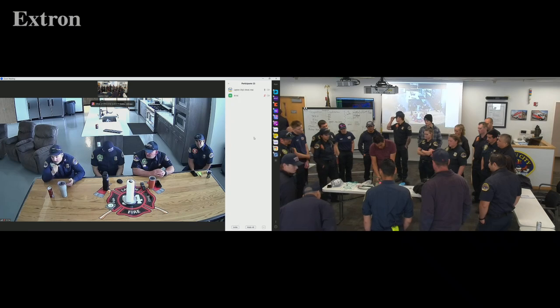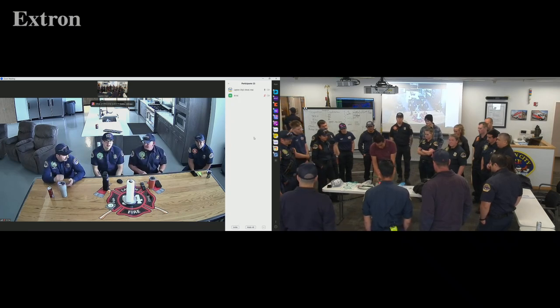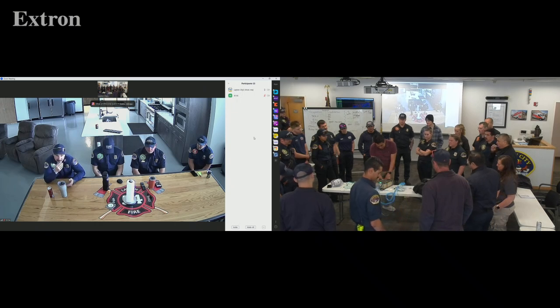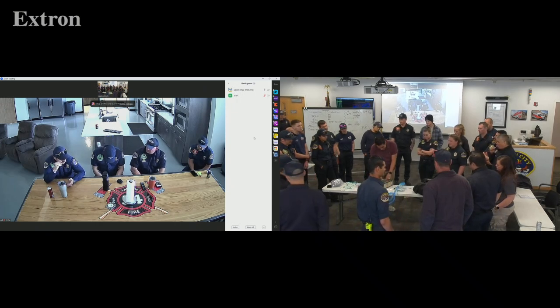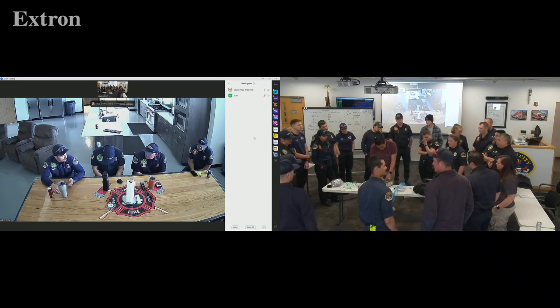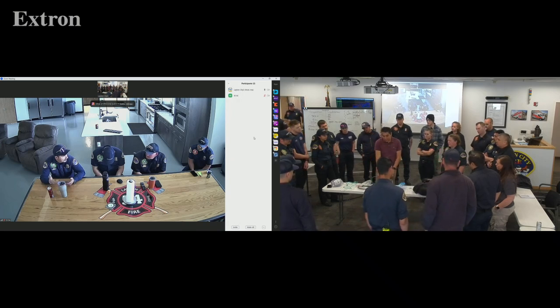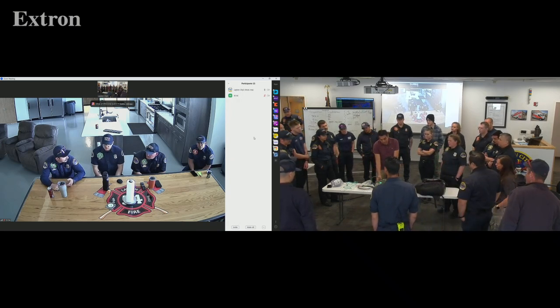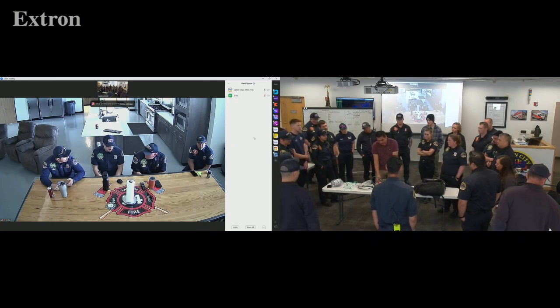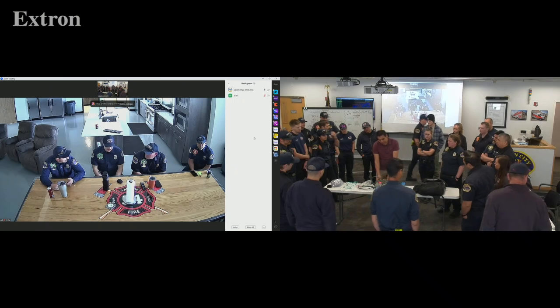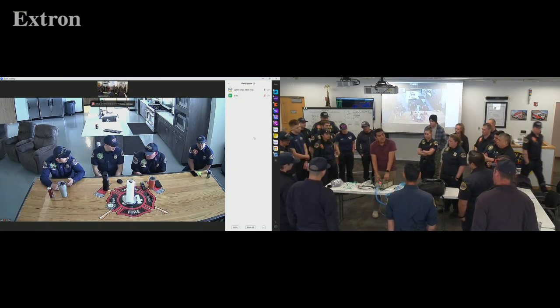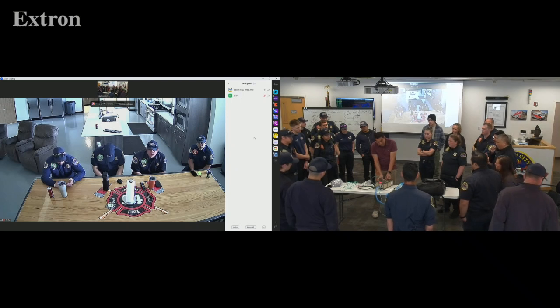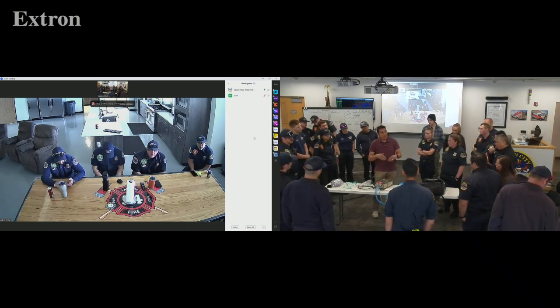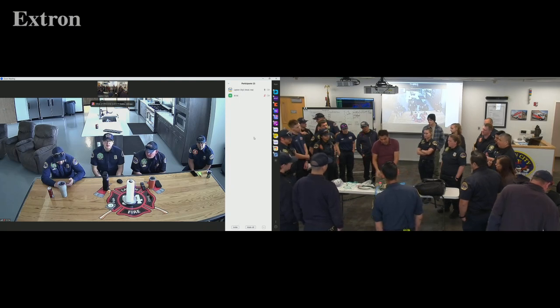Come on, change the mode. I keep forgetting that you have to push forward. So once you choose bi-level, in the bottom right corner of your ventilator where it says the mode, you push and hold the button that's right next to it, and it's gonna take you to a mode menu. That mode menu has 3 numbers: PIP target, BPM, that's breaths per minute, and I:E ratio. In order to move the respiratory rate higher than what it said already, you have to move your PIP target higher than that. So select that, and then you move your PIP to 25.